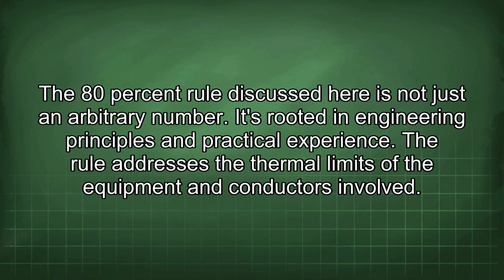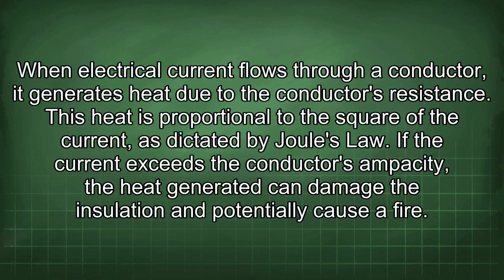The 80% rule discussed here is not just an arbitrary number. It's rooted in engineering principles and practical experience. The rule addresses the thermal limits of the equipment and conductors involved. When electrical current flows through a conductor, it generates heat due to the conductor's resistance. This heat is proportional to the square of the current, as dictated by Joule's law. If the current exceeds the conductor's ampacity, the heat generated can damage the insulation and potentially cause a fire.